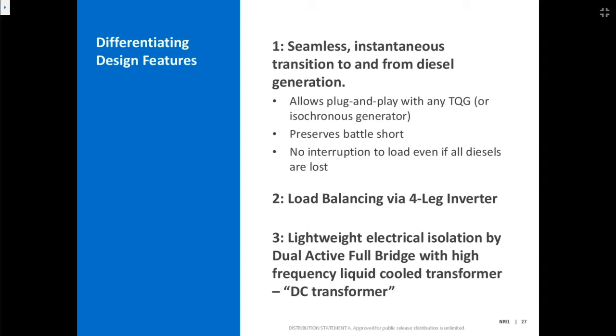However, the cube uses a really advanced inverter control technology and implementation that is linked with the contactor status of the TQG to seamlessly be able to parallel with that TQG output, or instantaneously pick up the voltage if that TQG went down for any reason, even unplanned. That's pretty hard to do in the inverter world. The team was able to design and build this and demonstrate that it's a viable technology that performs very well.